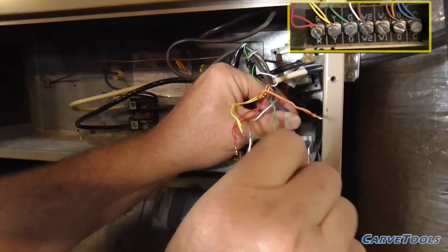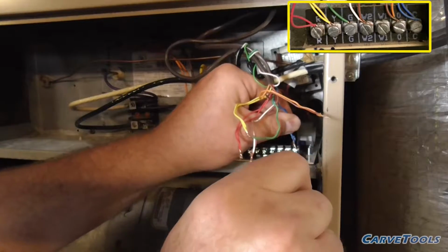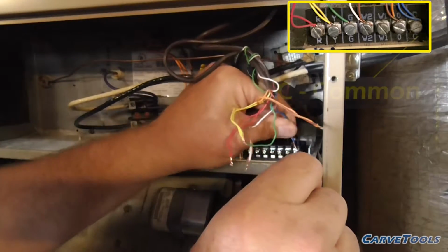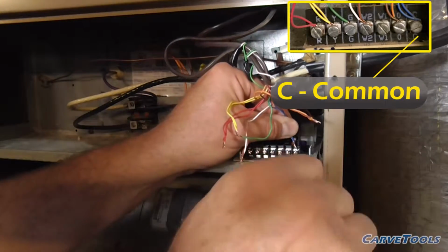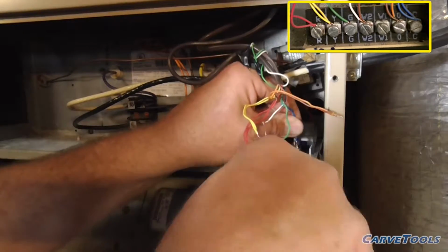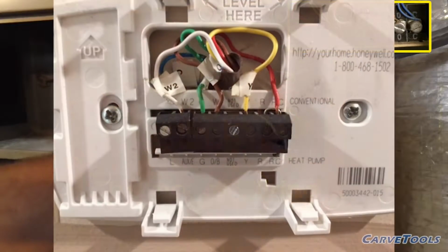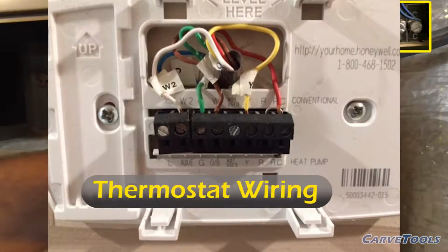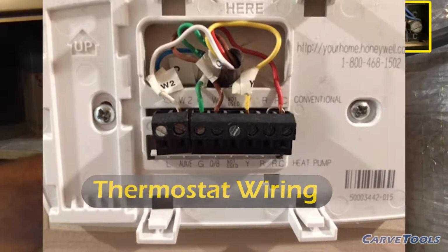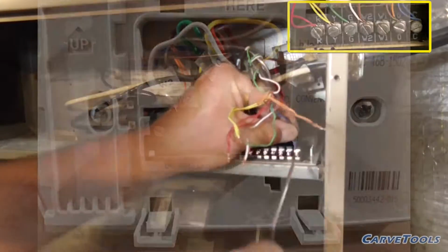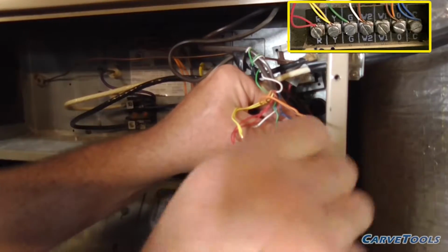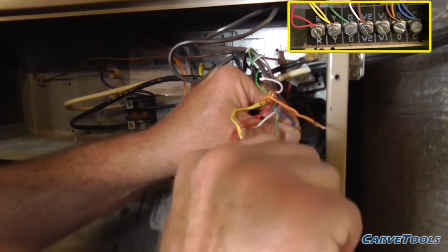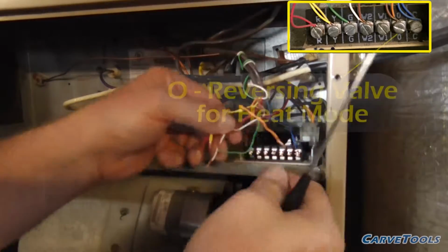and I will refer to my photo to make sure I put them on the correct terminal. Okay, I told you I'd tell you a little bit about each terminal. This is the C terminal, and it is the common for 28 volts AC. There are two blue wires twisted together. One goes to the outside unit. The other supplies power to the thermostat, but in my case, the thermostat is battery powered and the blue wire is not actually used. The O terminal, this is for the reversing valve in heat mode.